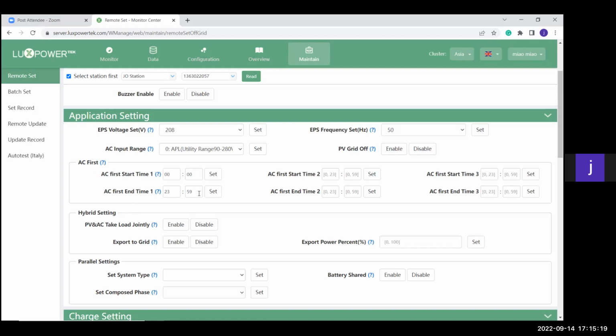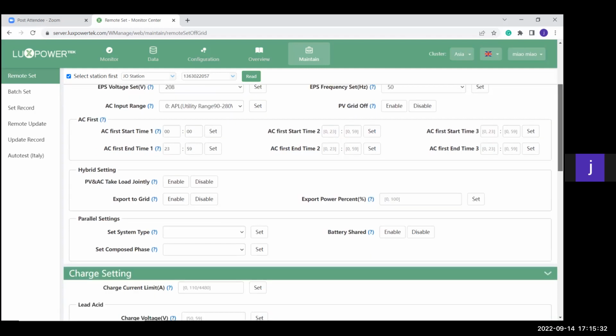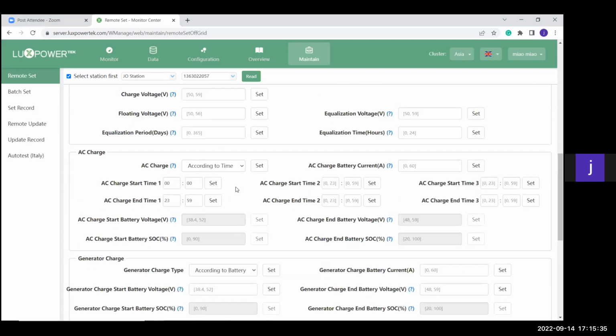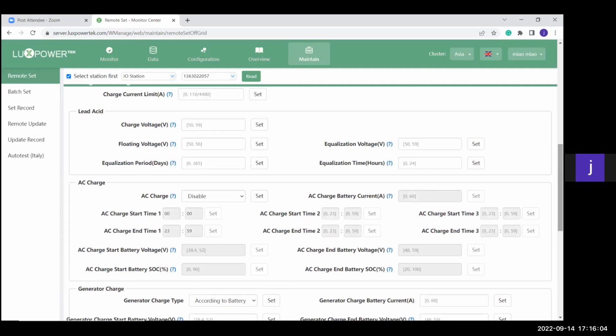So this was for a system that's running on solar, utility, battery. Just to recap that one: for solar, utility, battery, AC first is on, you enable the PV and AC jointly function, and AC charge you can also enable. But if you don't want your batteries to be charged by Eskom when there is load shedding, and you only want your batteries to be charged by solar, you can just disable AC charge, and tomorrow morning the solar will charge your batteries and then provide to the loads again. That was for solar, utility, battery.